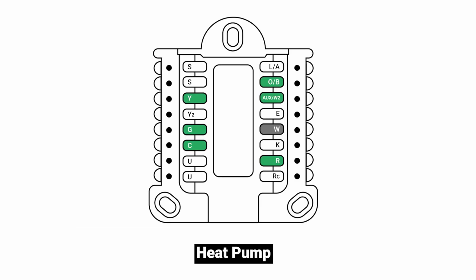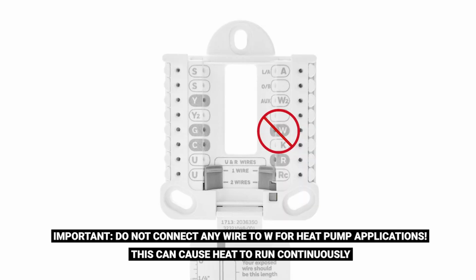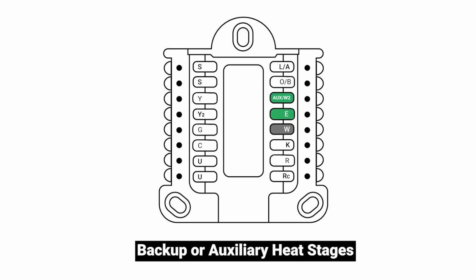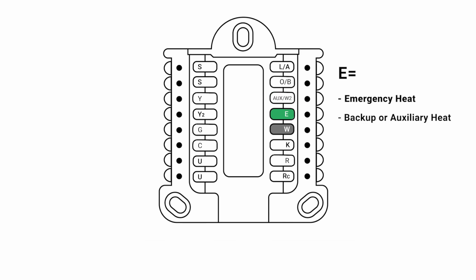For a heat pump system, the Y, G, and sometimes the O/B terminal will control the heat for your system. Again, if you have a heat pump system, you will not connect a wire to the W terminal. This can cause your heat to run continuously. Backup or auxiliary heat stages are controlled by the W2, AUX, and sometimes E terminal, depending on your configuration. The E terminal typically controls your emergency heat stage, and in some cases or configurations can also be leveraged with your backup or auxiliary heat.